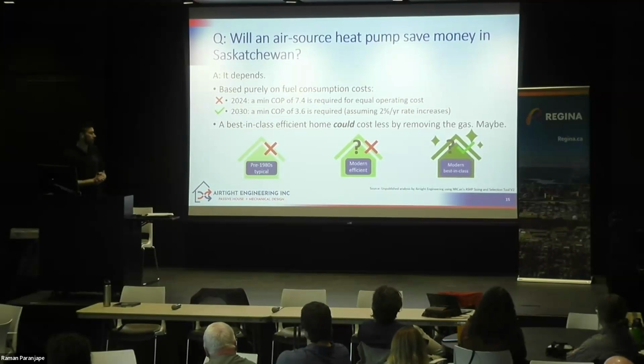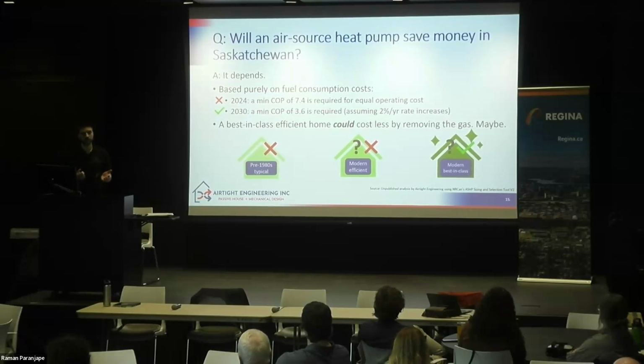By 2030, you would need a minimum COP of around 3.5 to 3.6. A big piece of that is the increasing carbon tax - gas is becoming more expensive because of it. So using that projection versus a heat pump, which is switching some of our heating to electricity, what does that look like? I was looking at some different models. A lot of heat pumps can do a COP of 3.6 down to maybe 0 degrees, maybe -5, a couple down to -10. But if you're heating above those temperatures, in that shoulder season heating, you'd be able to get that kind of performance, with bills in line with what you'd be paying for gas.